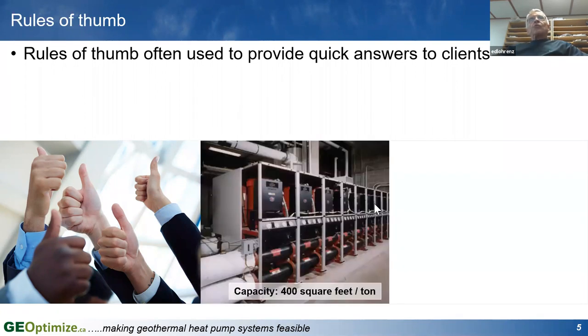There are two common rules of thumb that are often used. One is that the heating and cooling capacity required in the building is often based on how many square feet of building there is. The common rule of thumb is 400 square feet of building equals 1 ton of cooling capacity. And sometimes that's right, just like a clock that doesn't work is still right twice a day.